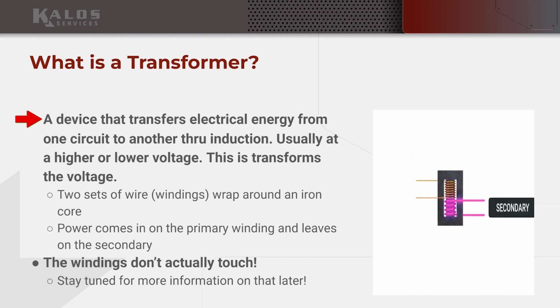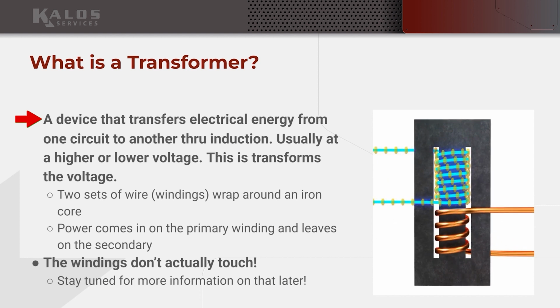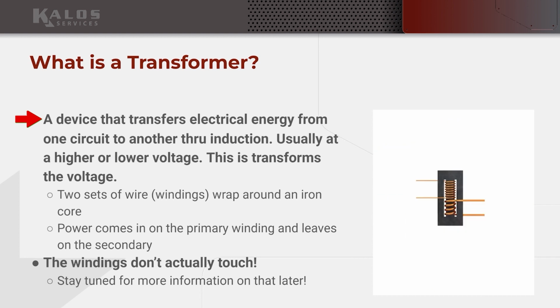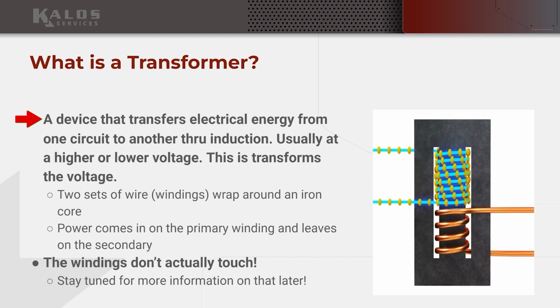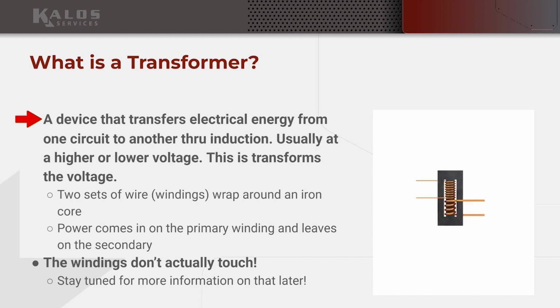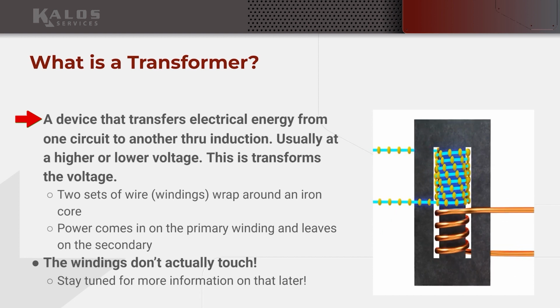Usually the incoming voltage is higher and the outgoing voltage is lower, although that's not always the case. That would be a step down transformer. You may have a step up transformer that takes a lower voltage and transforms it to a higher voltage. Or you might have an isolation transformer that takes the incoming voltage and gives you the same outgoing voltage, creating isolation in that there's no direct connection between the primary and secondary windings. The only coupling is through induction itself.